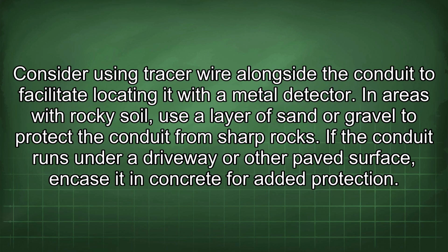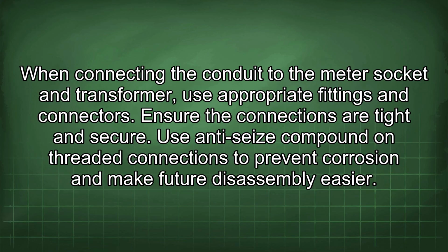Consider using tracer wire alongside the conduit to facilitate locating it with a metal detector. In areas with rocky soil, use a layer of sand or gravel to protect the conduit from sharp rocks. If the conduit runs under a driveway or other paved surface, encase it in concrete for added protection. When connecting the conduit to the meter socket and transformer, use appropriate fittings and connectors.